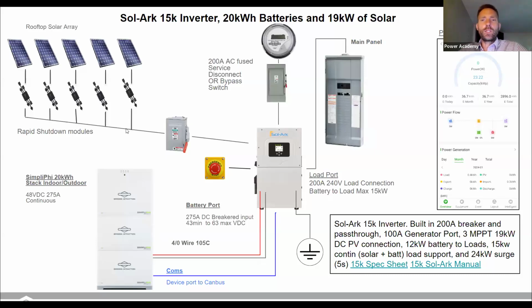Let's talk a little bit about what a wiring diagram or a quick single line diagram would look like for a Sol-Ark 15K. So a very typical example here, we've got some DC coupled solar in the top left that's feeding in through a disconnect here, going into your Sol-Ark 15K. We've got our battery feeding in. You've got communication coming from that battery going to the Sol-Ark 15K. And then we also have our utility connection. So our utility connection, we're going to come through a service entrance rated 200 amp fused or breaker disconnect. That 200 amps would come into that Sol-Ark, and then all the loads of the house would be fed out of the load port, the 200 amp load port in the Sol-Ark 15K.